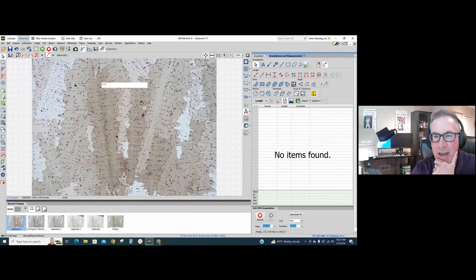Then we get into this whole row you see here, basically 10 different ways of measuring length. As I click, the first choice is 2 clicks to give me the length, or click and drag, measurement between 2 parallel vertical bars, 2 parallel horizontal bars, or 2 parallel lines at some angle. And as I capture these length measurements, you can see it dropping into this table over here on the right. So it'll accumulate the individual measurement data as well as the statistics down at the bottom here. So we've got mean, min, max, standard deviation all being captured.